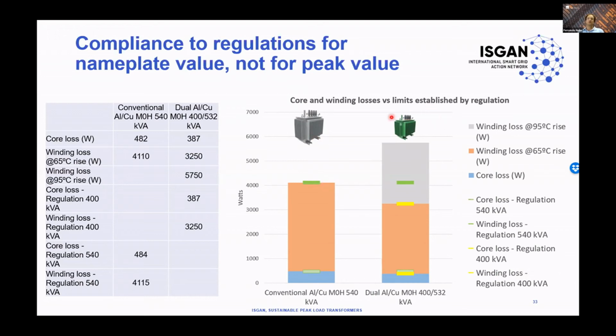If we look at the reduced size unit, then the nominal, or the base nameplate, is 400 kVA. And then if we represent in yellow the limits established for core losses and winding losses, we see that this unit is compliant with both. But of course, if we represent in gray the winding losses at 95 degrees Celsius rise, these are much bigger. So these are well beyond either the 400 regulation or the 540 regulation.